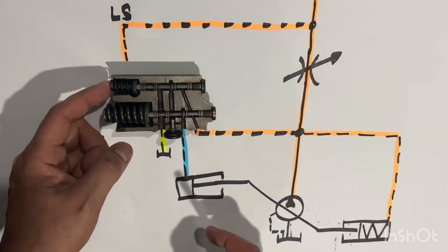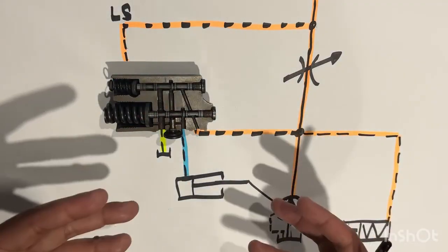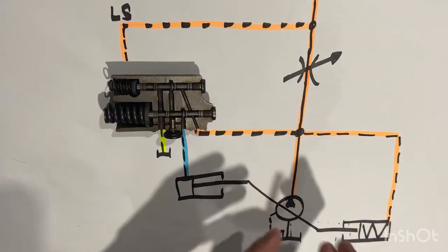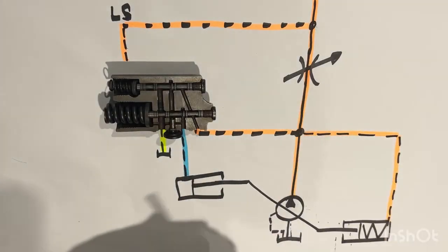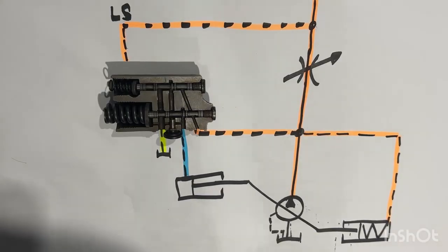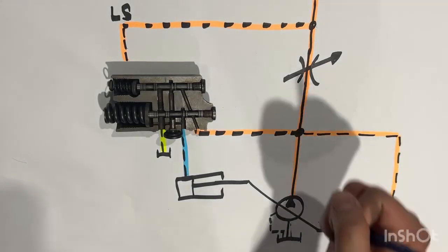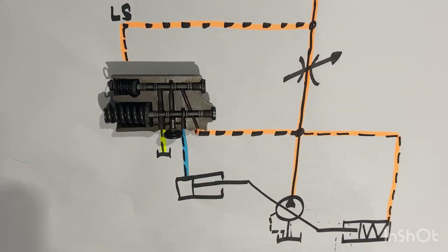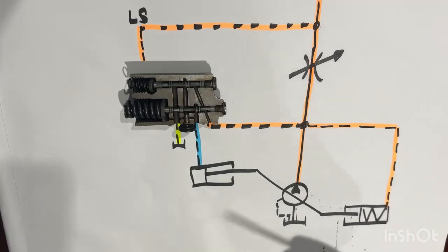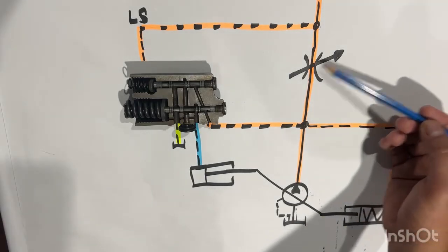All right. So this load sense control, this system here, the pump will give flow only according to the demand. So if the operator wants 50%, the pump will give 50%. Why? Because it will maintain the pressure differential across the delta P. Alright, so another condition. If the operator totally closed the control valve, not using it anymore, so what happened? Okay, now if there's no use, the control valve is fully closed.